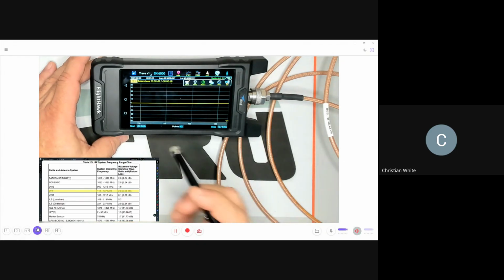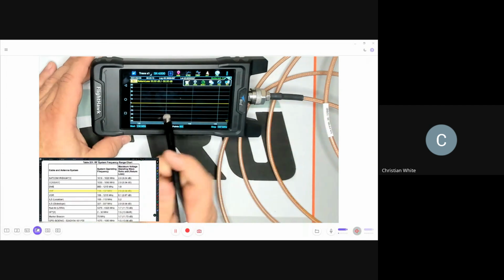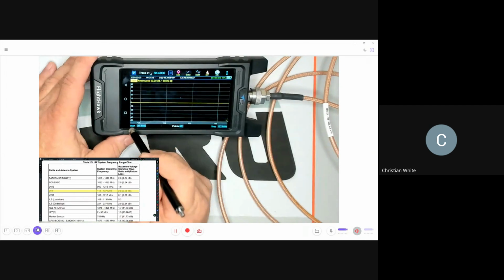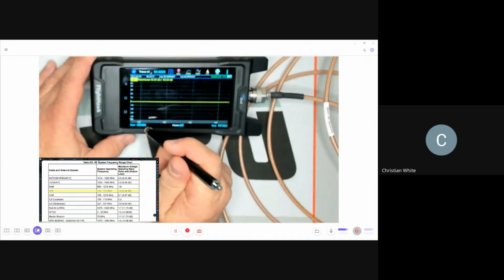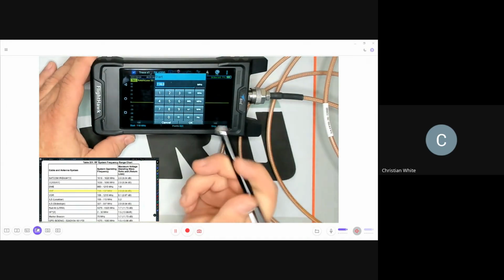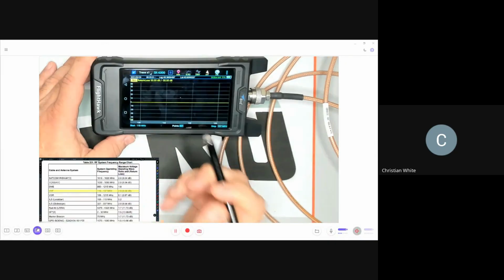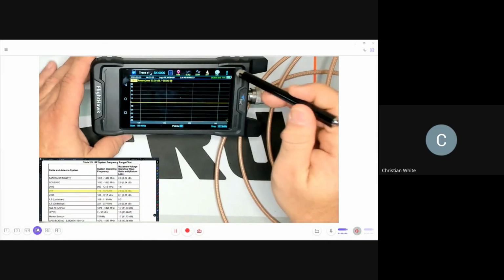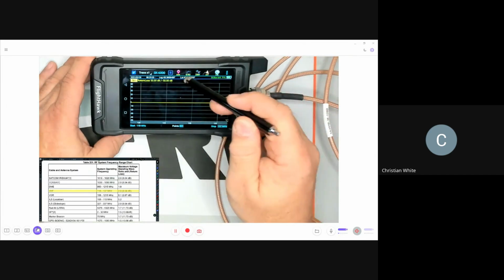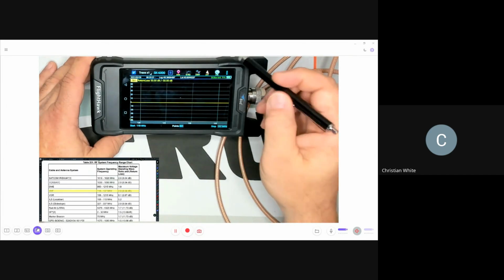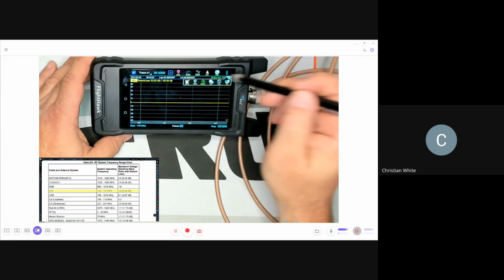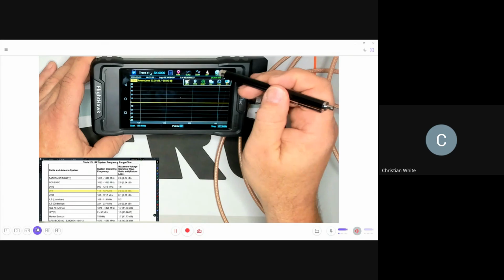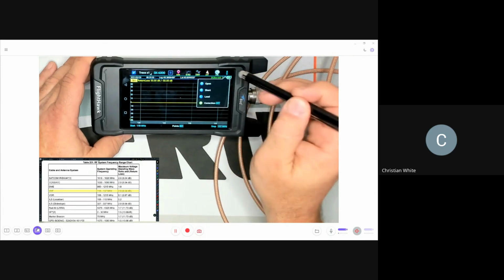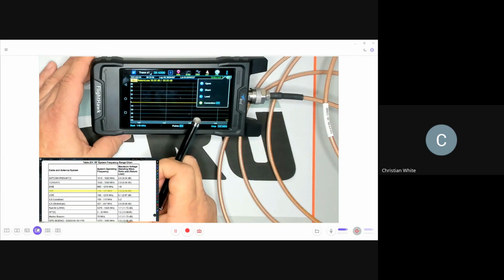Okay. There are shortcuts here at the bottom. If you just click on start, you can put it in directly there if you want. But it's easier to remember right to left on this menu, and that's how you do setups. So we did this, we did our frequency. Now our next thing over here is cal. Anytime you change the frequency on here, you need to do a new calibration.